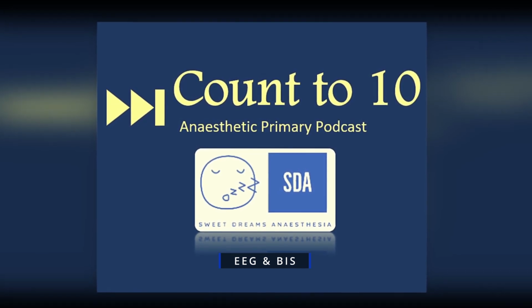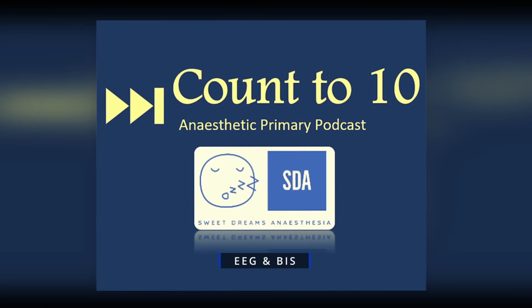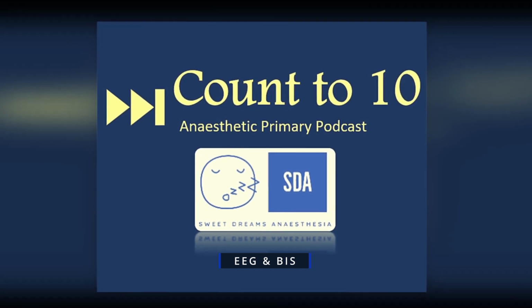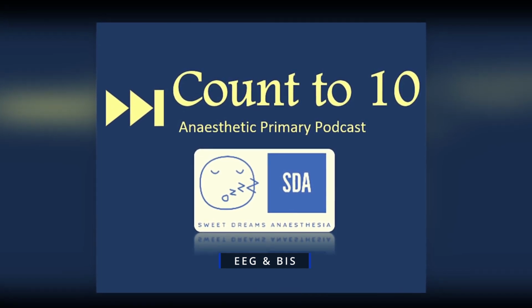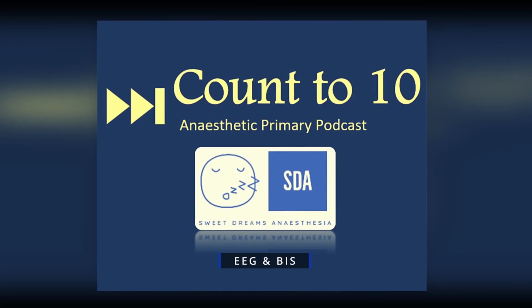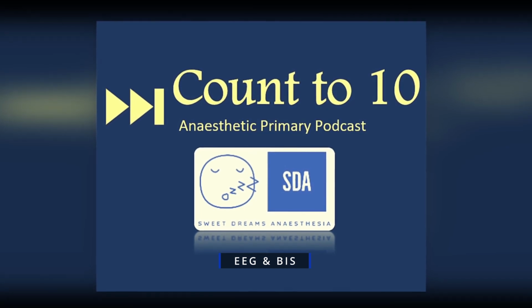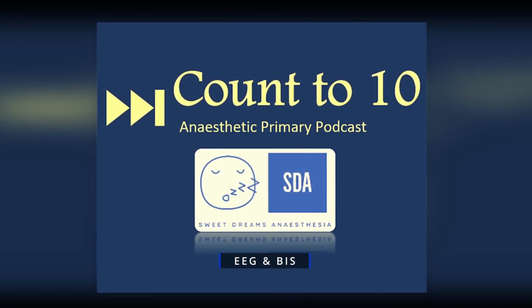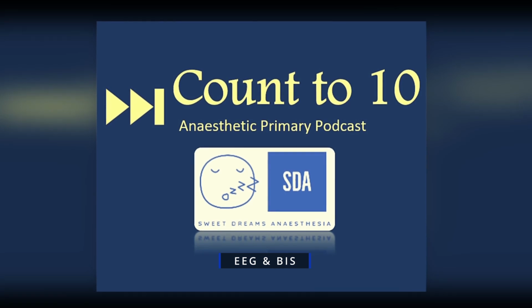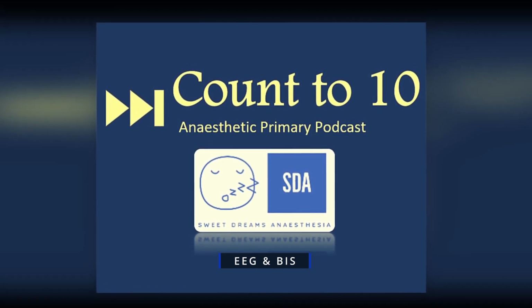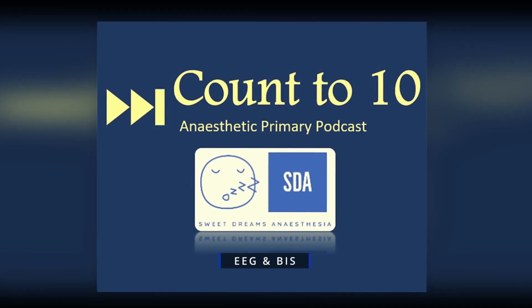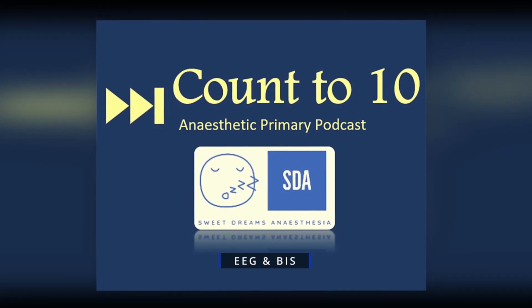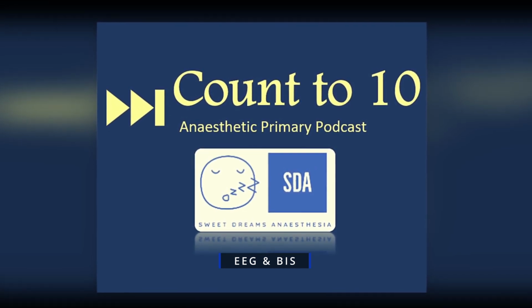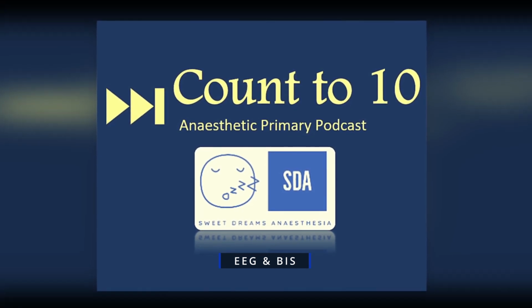This gets us on to talking about what types of processed EEG monitors there are, and by far the most common and the most widely used is BIS. BIS stands for Bispectral Index Monitor, and it's a complex statistical analysis through Fourier transformation. Essentially, it's doing two things. It's giving us a dimensionless number from 0 to 100, and it's giving us a waveform.